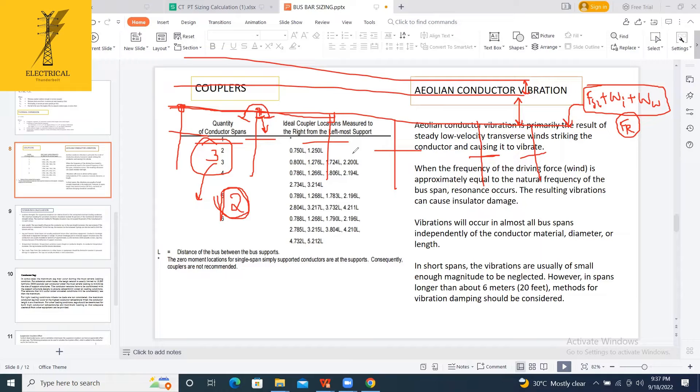I concluded the sizing calculation of the rigid busbar. See, rigid busbar sizing, generally outside, they will only calculate the aluminum tube. That's it. They won't calculate all these things. They generally go ahead with 3 meter spacing, 4 meter spacing. Based on past projects, they are moving ahead. But the actual way of doing rigid busbar sizing is this.